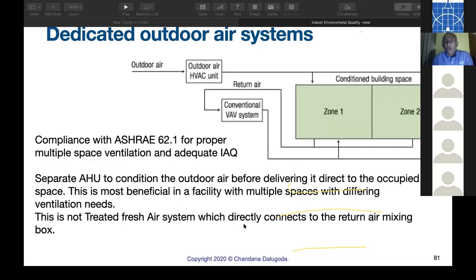Now, the idea of this dedicated outdoor air system by Mr. William J. Coad, ASHRAE President, 2002 probably. He came to Sri Lanka. Now he thought in big air conditioning systems, the outdoor air component is large. Outdoor air is brought to the air handling unit and the coil will have to be sized to handle all this latent load in vain. Why not handle outdoor air separately, room separately? That was the idea.